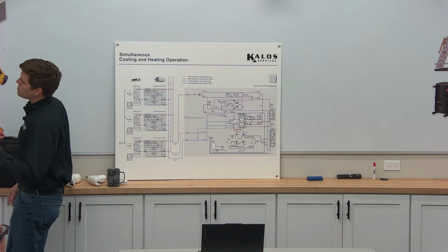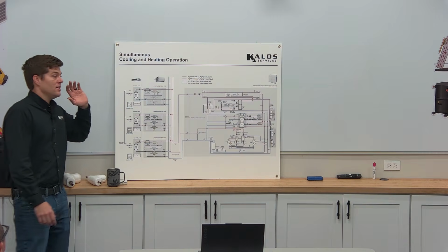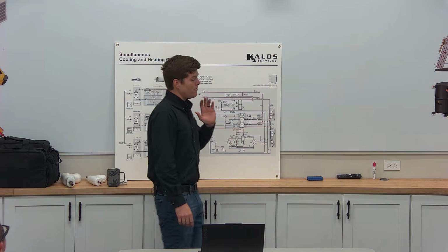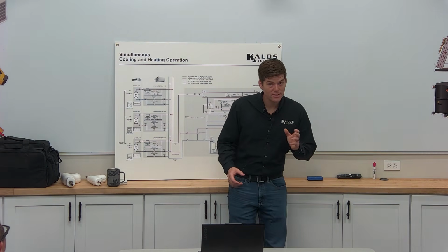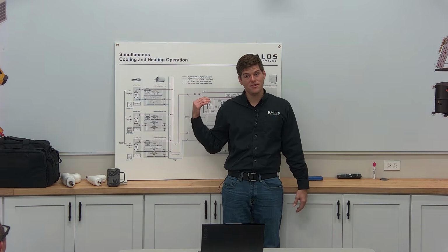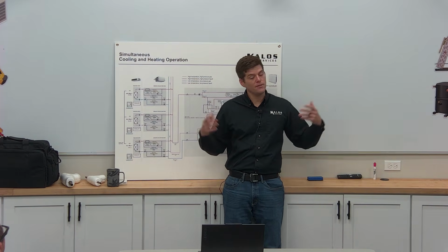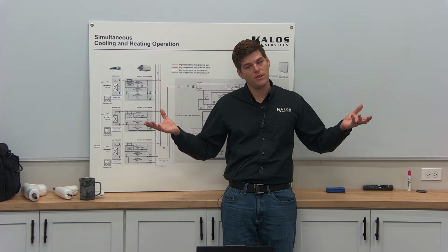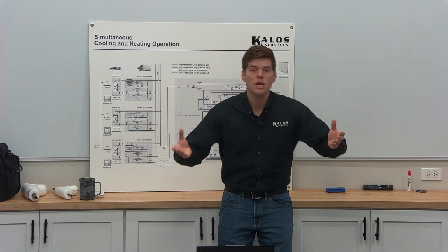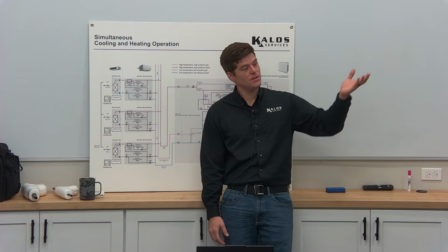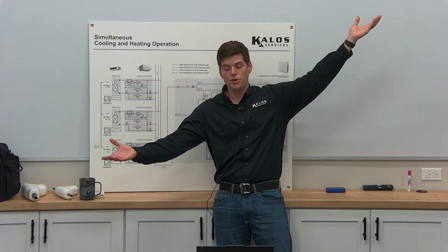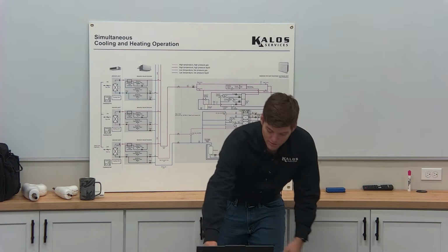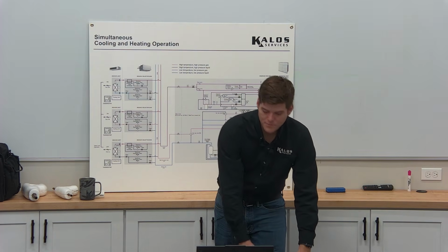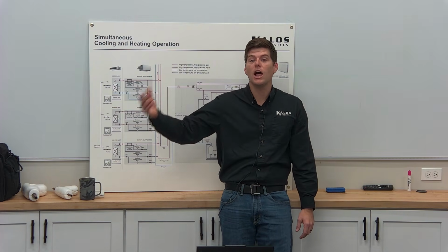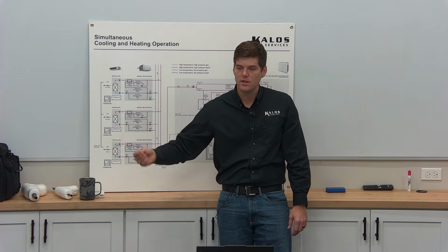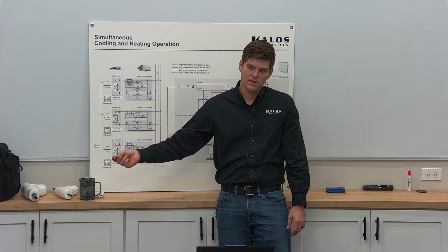So the variable, we've got 168 different compressor speeds, which allows us to move a large amount of refrigerant flow to the indoor units, right? Daikin uses volume. Technically, volume and flow, if you want to split hairs, are completely two different things, and they're measured in different ways. But it's all about the same thing. It's about a system, an outdoor unit, whether it's one indoor unit, 5 indoor units, or 6 indoor units. It's designed to supply a specific amount of refrigerant to those units at any given time.